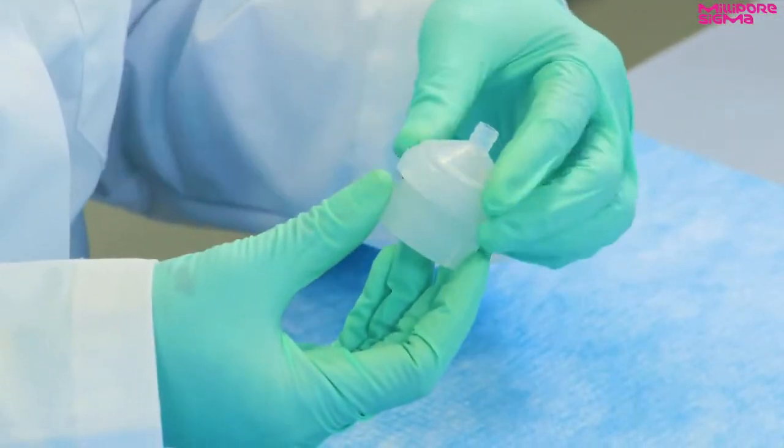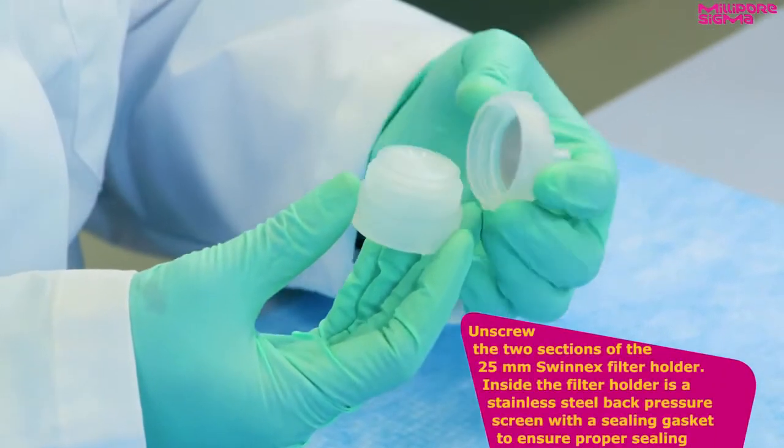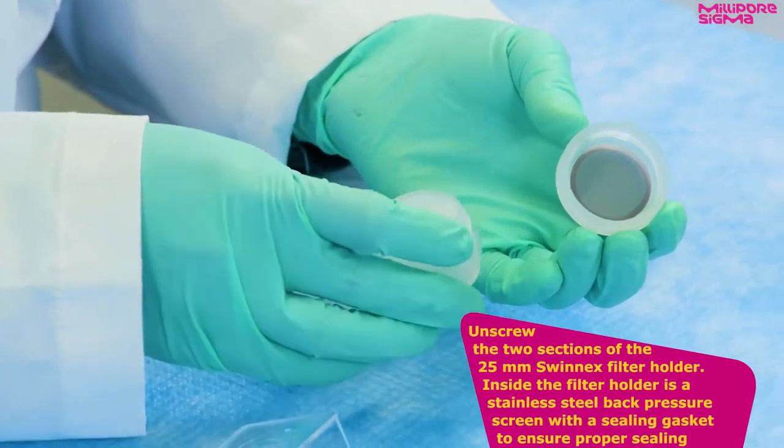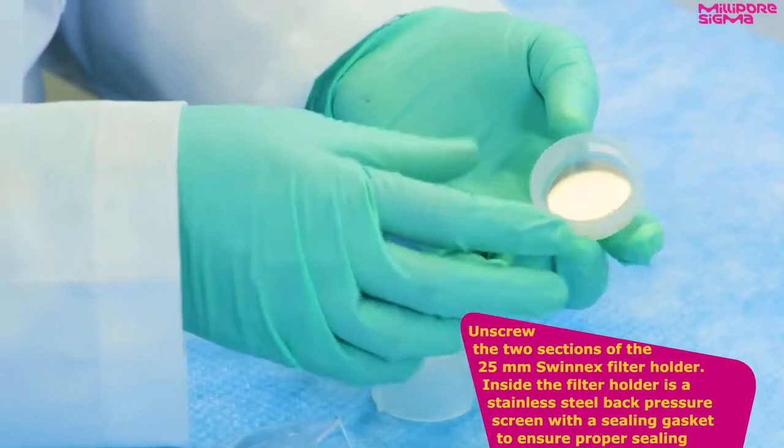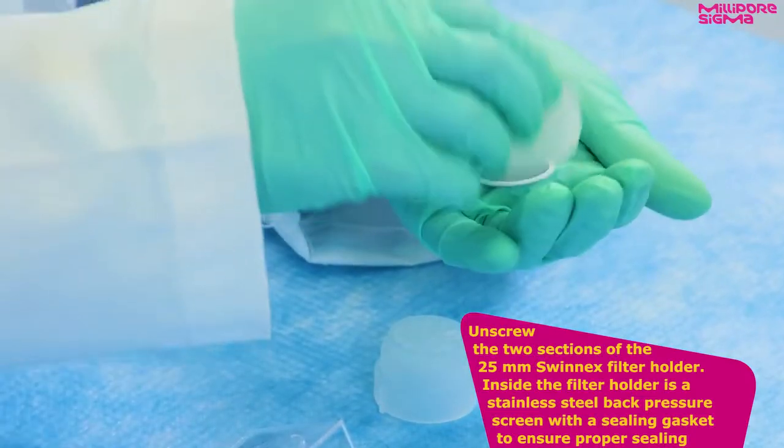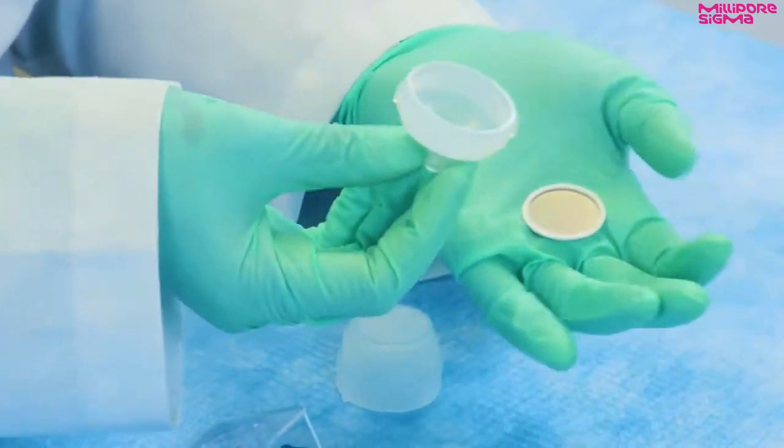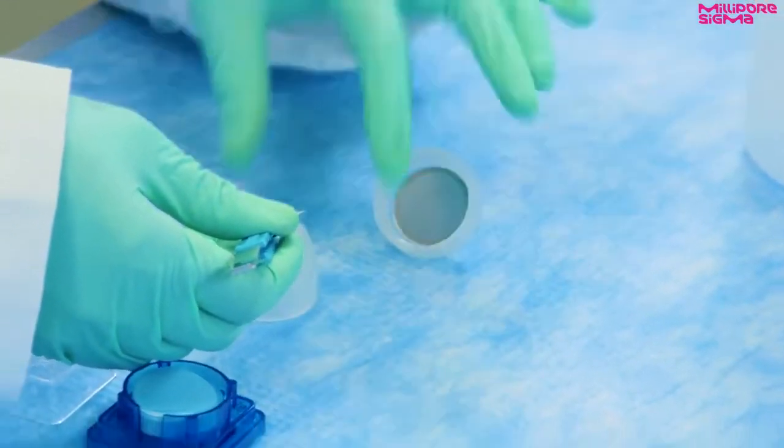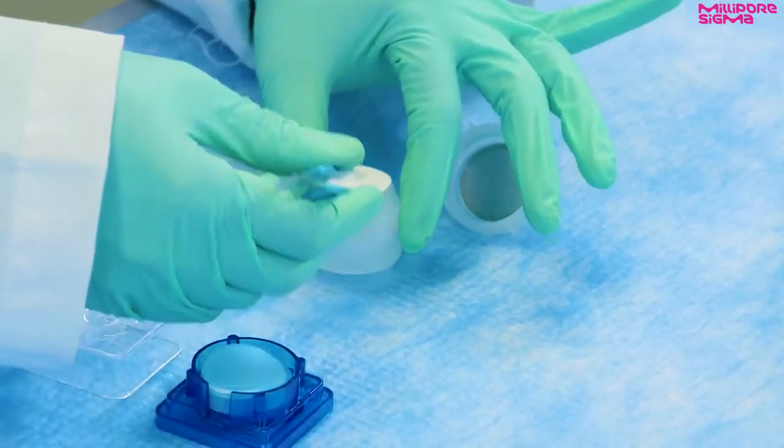To prepare the filter for rinse solvent, first unscrew the two sections of the 25 millimeter Swinnex filter holder. Inside the filter holder is a stainless steel back pressure screen with a sealing gasket to ensure proper sealing. Use forceps to center a 25 millimeter white filter disc on the perforated plastic support in the lower section of the filter holder.